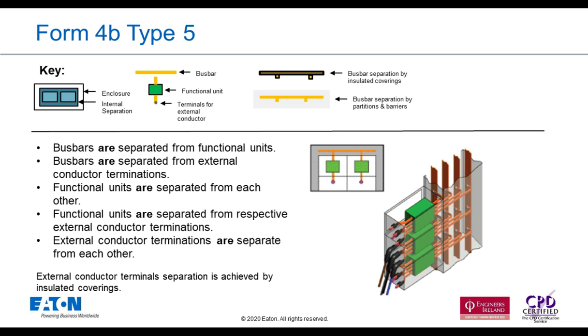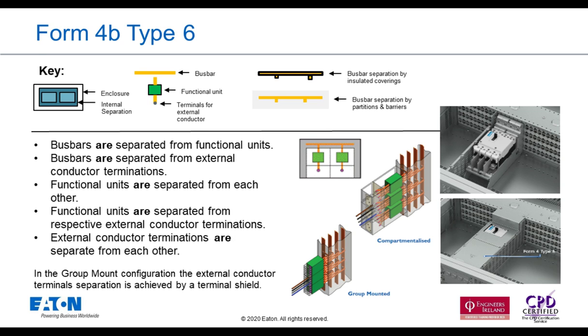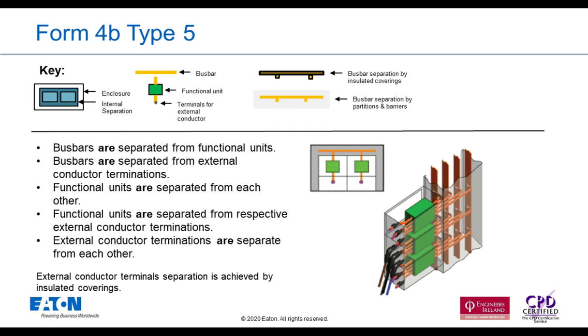So Form B Type 5. Here, you can see from the picture that the external cable terminals exit the functional unit compartment, but then there's, I would say, a common cableway for argument's sake. What we're doing is using some insulated boots to cover each terminal to provide that separation to comply with Form B. Just on the previous one, Type 5, you don't normally see this type of setup, or I certainly haven't come across this. I've never seen it really in any specs out there, so it's quite unusual.